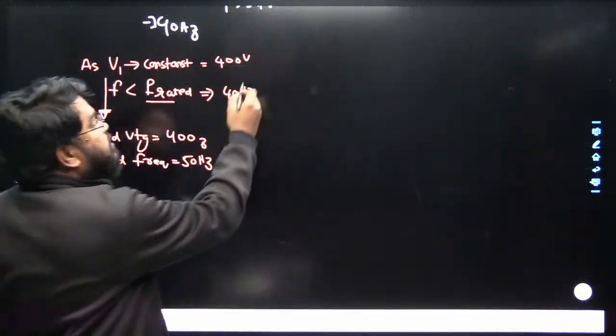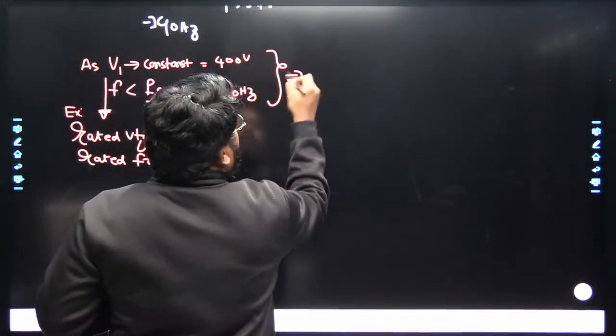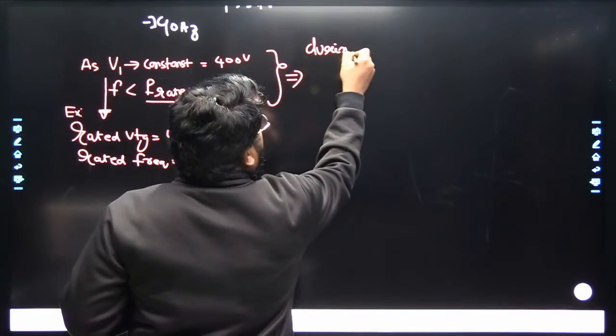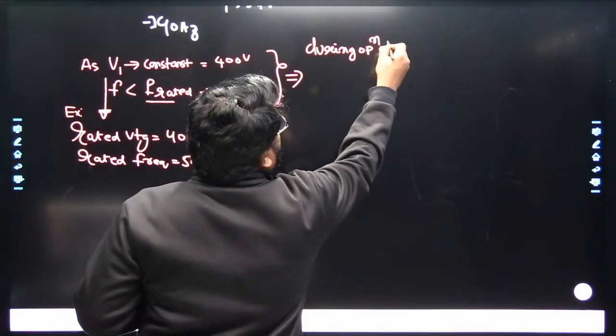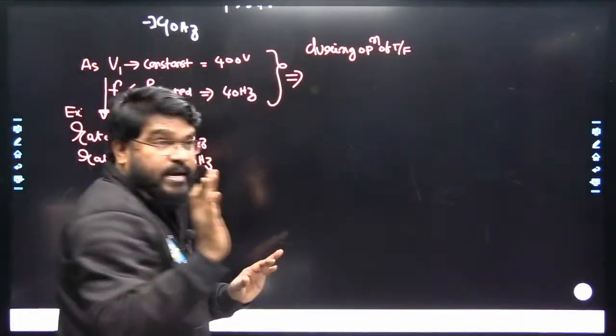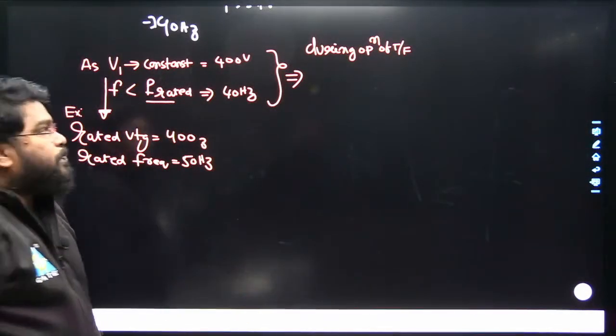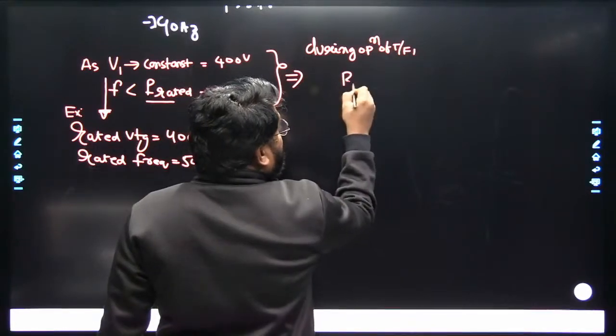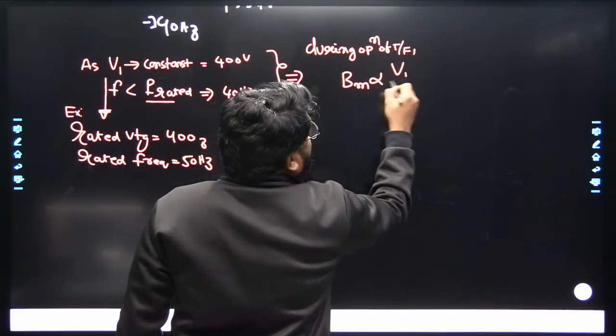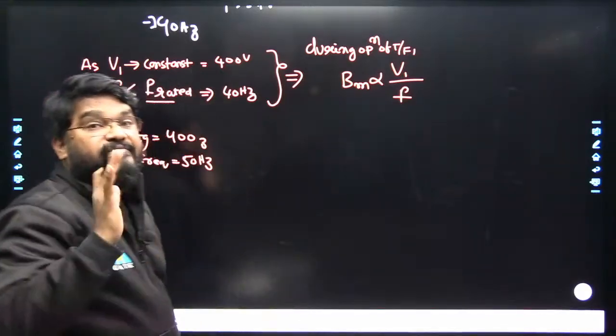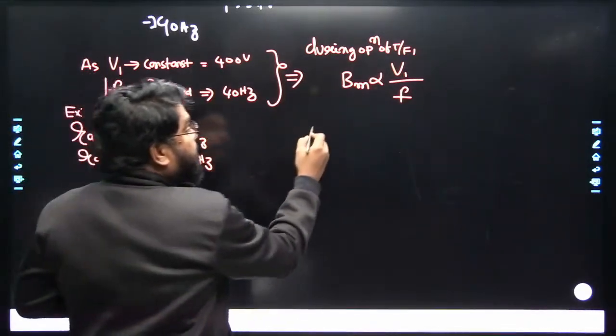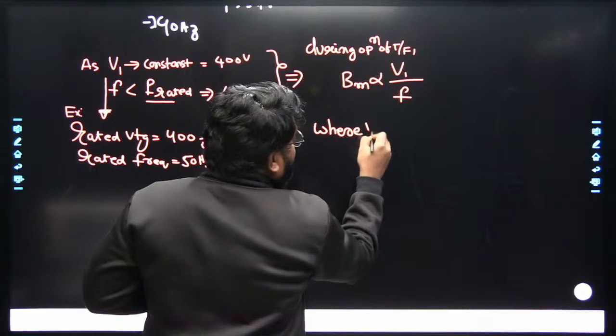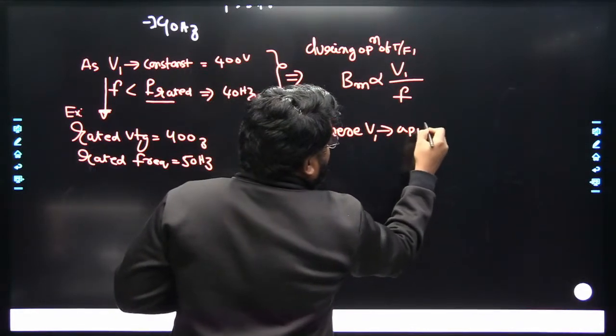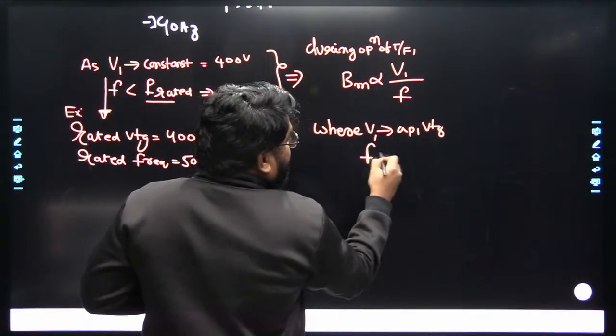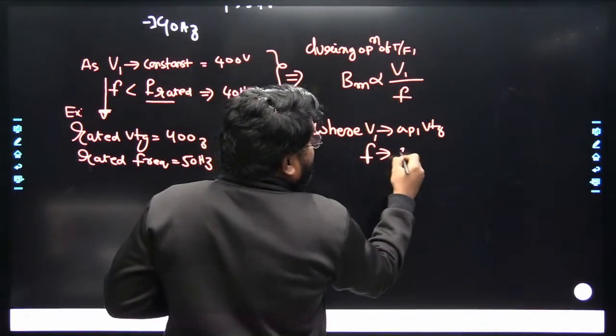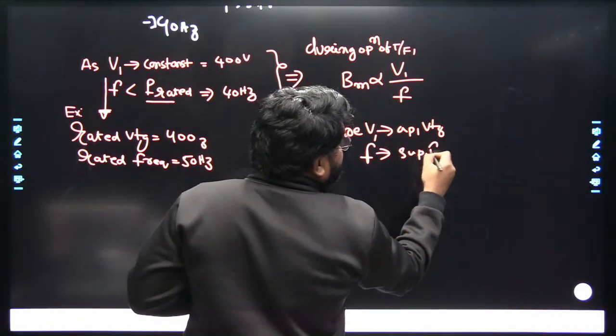During operation of the transformer, the flux density of the transformer core is directly proportional to the V1 by F ratio, where V1 is the applied voltage and F is the applied supply frequency of the transformer.